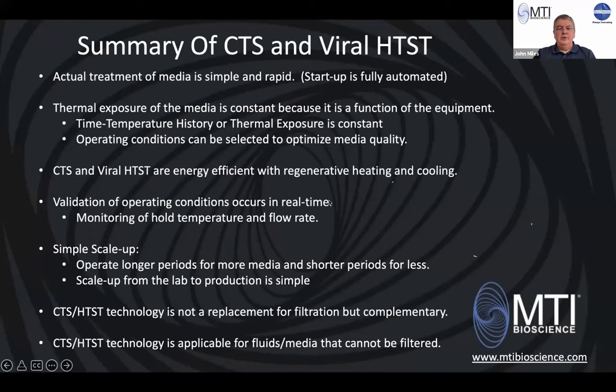Validation of the operating conditions—this is the big point I made earlier—when you're doing a filtration process, you have to validate offline and stop. Validation of these processes is done in real time. We're always monitoring the temperatures, the flow rate, and the operating conditions, and those things are all alarmed so we know what's been delivered, that it's the right way, and we have the records to show for it. So validation for these processes is in real time.